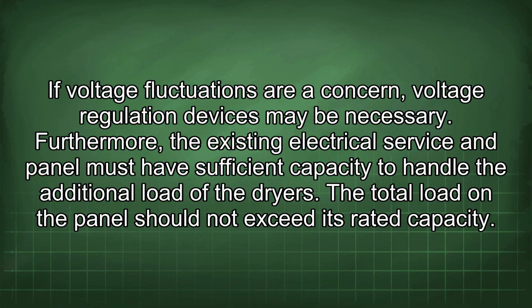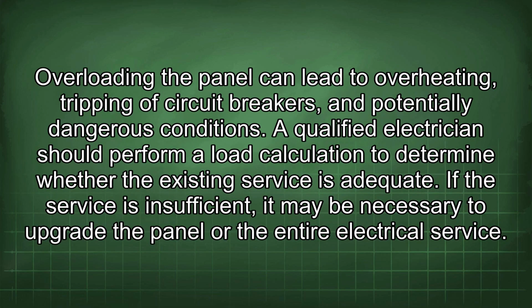Furthermore, the existing electrical service and panel must have sufficient capacity to handle the additional load of the dryers. The total load on the panel should not exceed its rated capacity. Overloading the panel can lead to overheating, tripping of circuit breakers, and potentially dangerous conditions. A qualified electrician should perform a load calculation to determine whether the existing service is adequate. If the service is insufficient, it may be necessary to upgrade the panel or the entire electrical service.